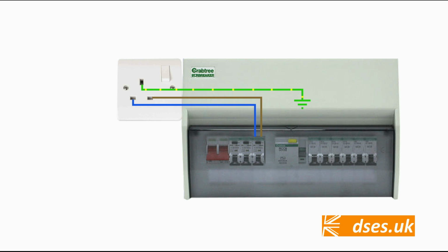Mandating AFDDs would mean I'd have to install such here, which would be a nonsense. The intended load is never going to be high enough to cause an arc fault. Only if someone plugs in an iron or kettle and a loose connection has managed to form on this very simple circuit would it be needed. As the designer of this solution to the client's needs, it makes no sense to go to the expense of installing a computer into this consumer unit to monitor the trickle charging of someone's Dyson, especially if the CU lacks surge protection, and I'm not sure I trust the electronics in an AFDD to last long in a non-SPD board.